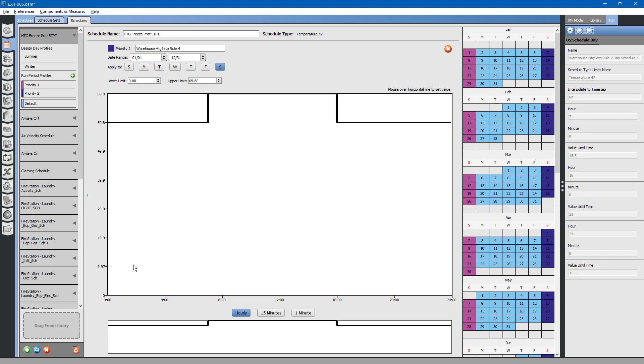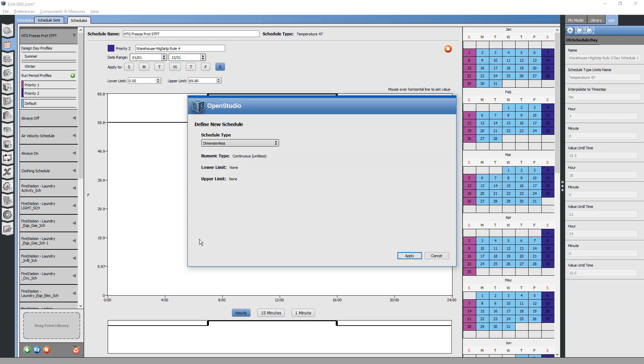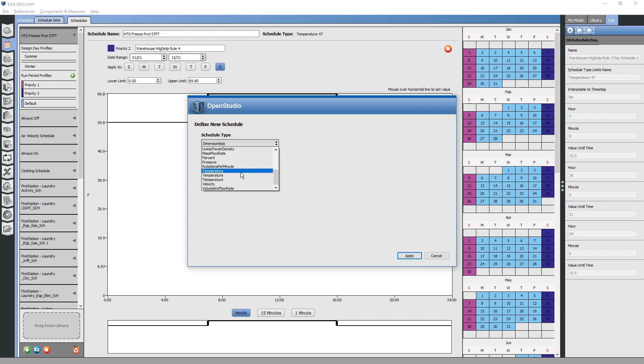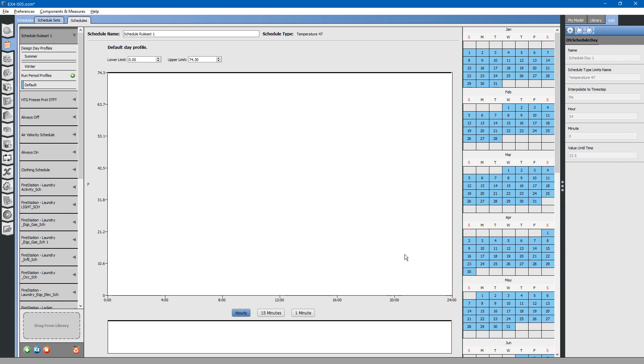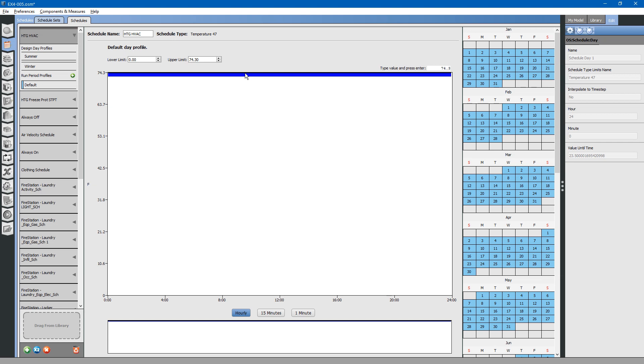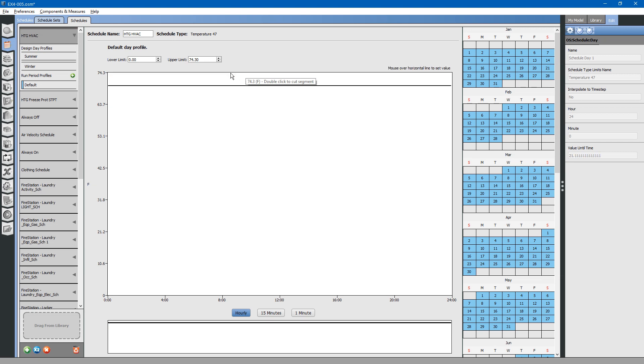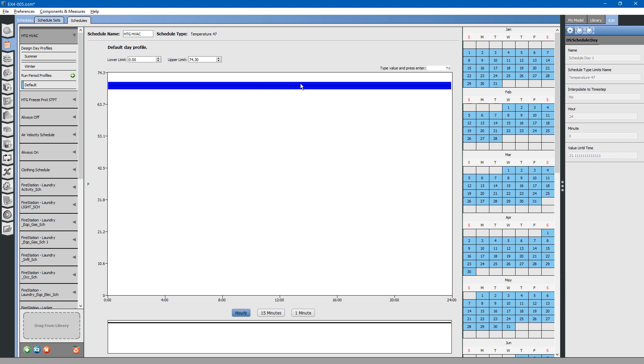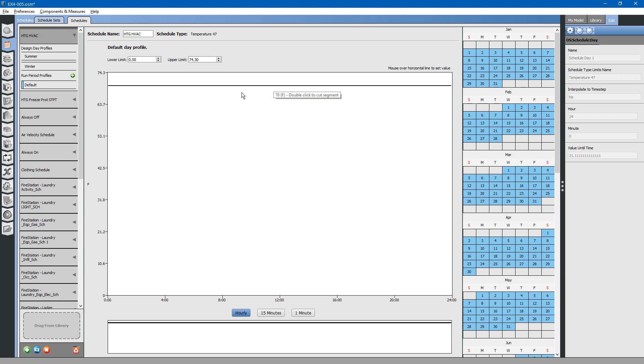Let us create an HVAC schedule for heating. Click the plus button. Select the type of schedule, temperature. Click apply. We will call this heating HVAC. The building is occupied 24-7 and operational 24-7. This will be a simple schedule. All we have to do is hover over the line and type in 70 degrees, basically room temperature. That tells the HVAC equipment to maintain the space temperature throughout the entire 24 hours of the day at 70 degrees.